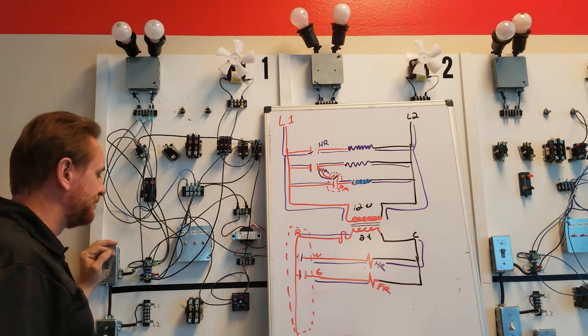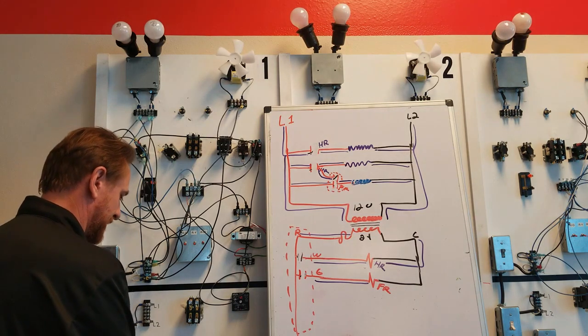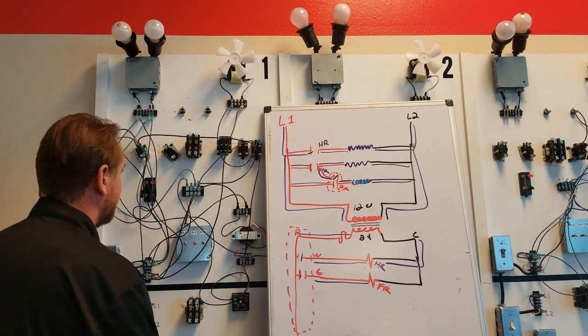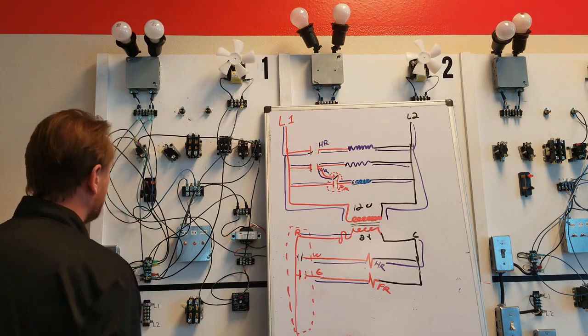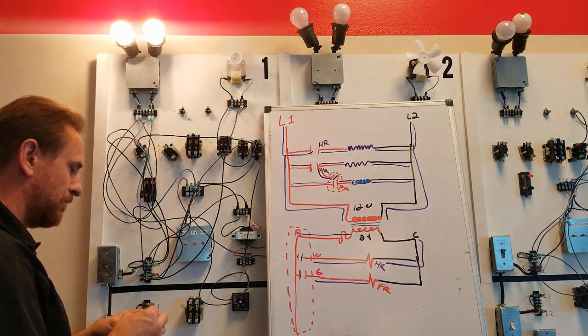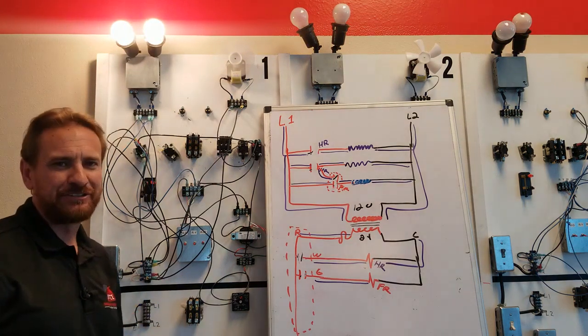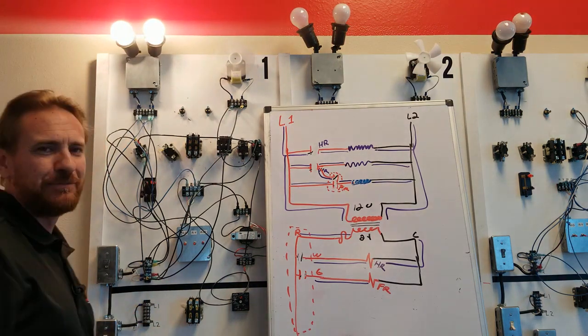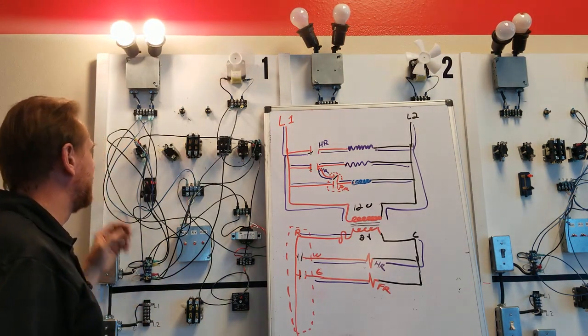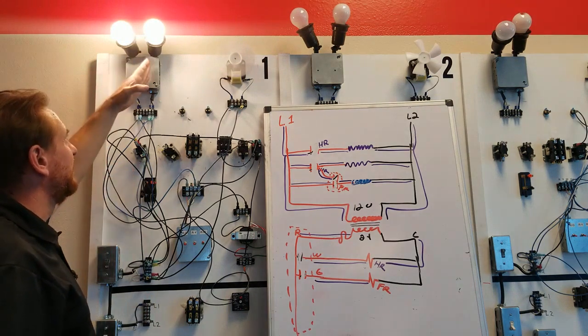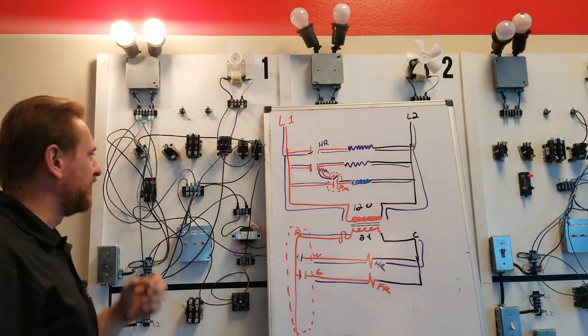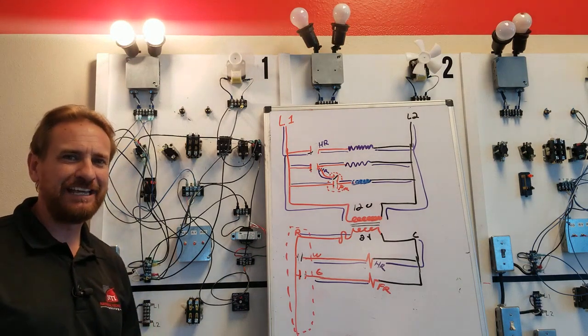So we got to think, what in the world happened to make this not work correctly? What everybody does is they go through the wires, they panic, they try to see what they did wrong. By the time they start pulling a wire, everything comes on. It did not come on immediately because this is a sequencer. It brings these on in a sequence. It also is a thermal time delay relay.